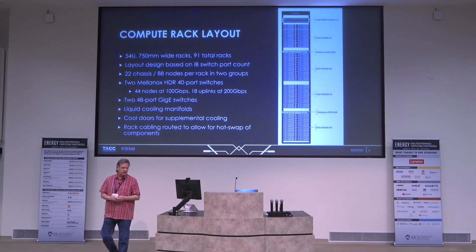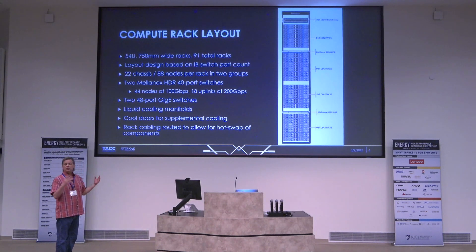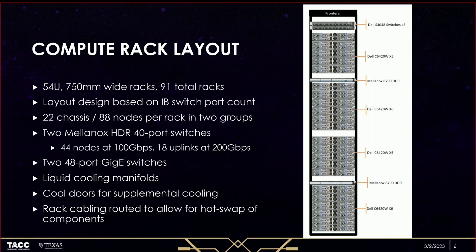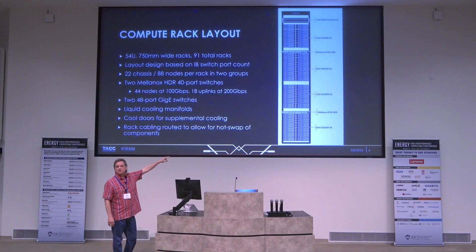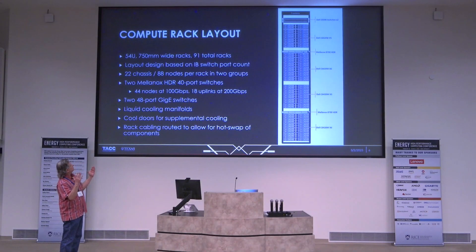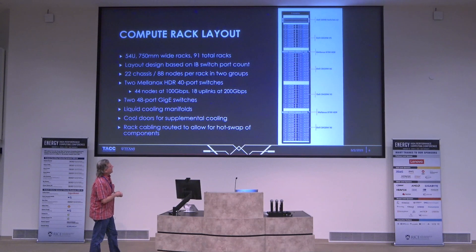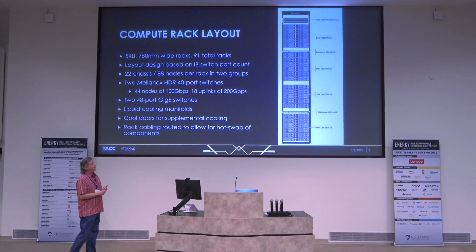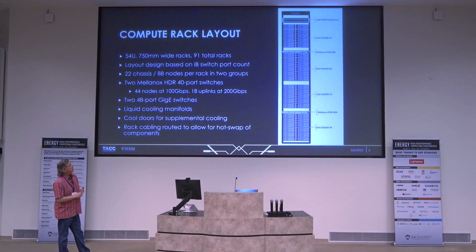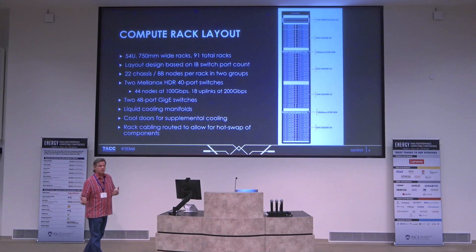The racks themselves require careful planning around cooling. We've had to go to very deep racks — about five and a half feet deep — to accommodate power distribution, networking, and chilled water distribution in the back of the rack. Every single node has its own connection to the liquid manifold. We've basically added a caboose to the back of the rack just to provide room for the manifolds to do the liquid cooling. This is something to keep in mind when designing and planning these systems in the future.